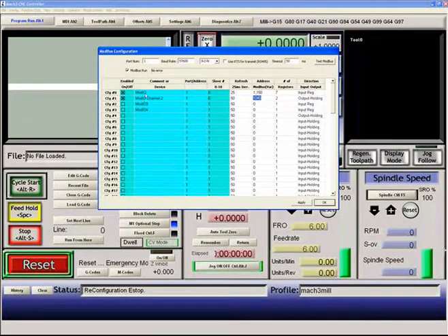So here I'm doing 2 operations. Every 25 milliseconds, I'm sending 7 registers from the PLC, or Mod I/O in this case, into configuration 0. And every 50 milliseconds, I'm sending 2 registers from configuration 1 to the Mod I/O on address 1040. So using this screen, you can set up 64 different configurations of Modbus data. And each configuration has 127 words of data maximum that you can use.